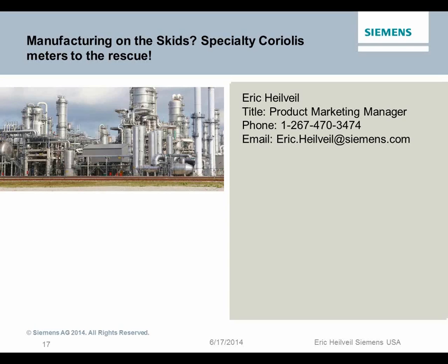There is a question here: which Endress+Hauser models would we most closely compare to? 83F. It's astounding how close it is. I think they used it as a benchmark. The 83F by Endress+Hauser is a very, very good Coriolis flow meter with a lot of functionality. Not quite as much, of course, as the Siemens has, but we just came out with it, and the 83F has been around for a while. It is a good sensor, and there's no downside to it. It is the closest meter to the Siemens meters.